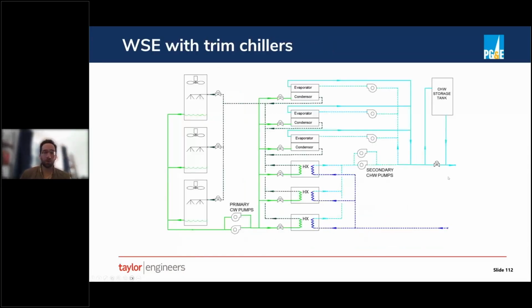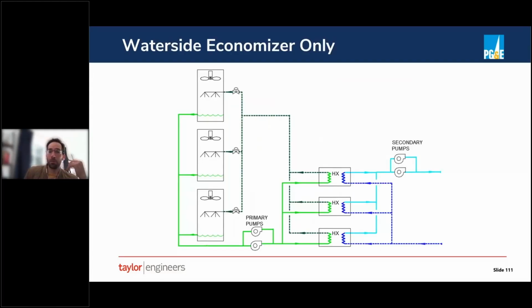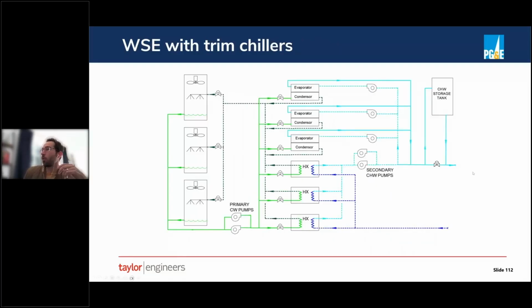And then what we typically do in most of our installations, because there are a lot of climates where we can't do just this waterside economizer only option, but they're pretty much any climate we're going to operate in. We don't want to just do chiller only because that's going to be very inefficient for a lot of the year. So we'll meld the concepts together and do something like this, which is a waterside economizer system with trim chillers. This looks actually a lot like the previous slide, but what we've added to the system is a set of chillers that are downstream of the waterside economizer in the chilled water loop.